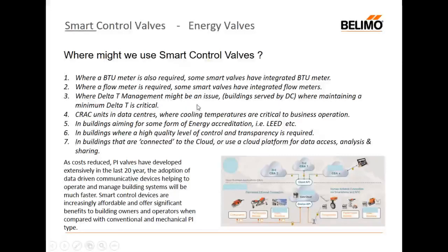Where delta T management might be an issue, buildings served by district cooling spring to mind, where maintaining the minimum delta is absolutely critical to the costs of running the building. And the building owner doesn't want to face district cooling penalties because the delta is too low. So having a valve that can manage that would be helpful. CRAC units in data centers, that's a growing and emerging business, and cooling temperature is absolutely critical to their efficient business operation, absolutely vital.